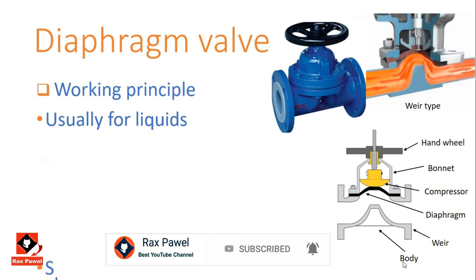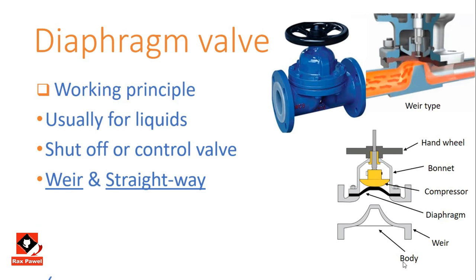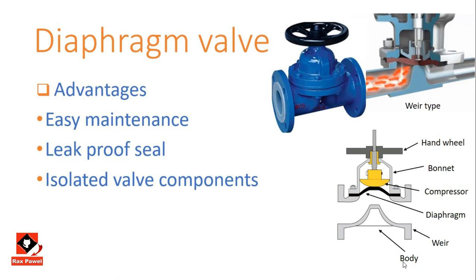Diaphragm valve working principles: it has a diaphragm moved by a compressor with the aid of a stem. Most of the time it is used for liquids, acting as both a shut-off valve and a control valve. There are two types: weir and straightway, with the weir type being most commonly seen. The pinch valve is an improvement of the diaphragm valve working on the same principle. Advantages: maintenance is very easy and it provides a leak-proof seal. Most importantly, valve components are isolated from the process fluid by the diaphragm, providing safety for valve components.